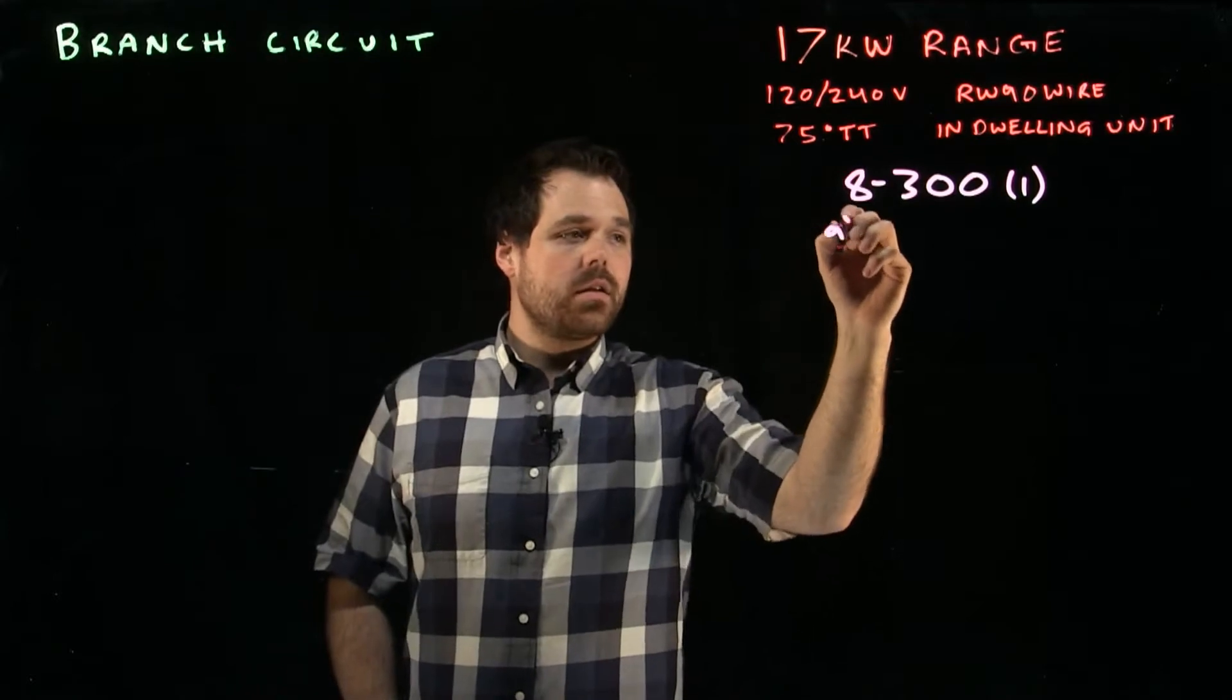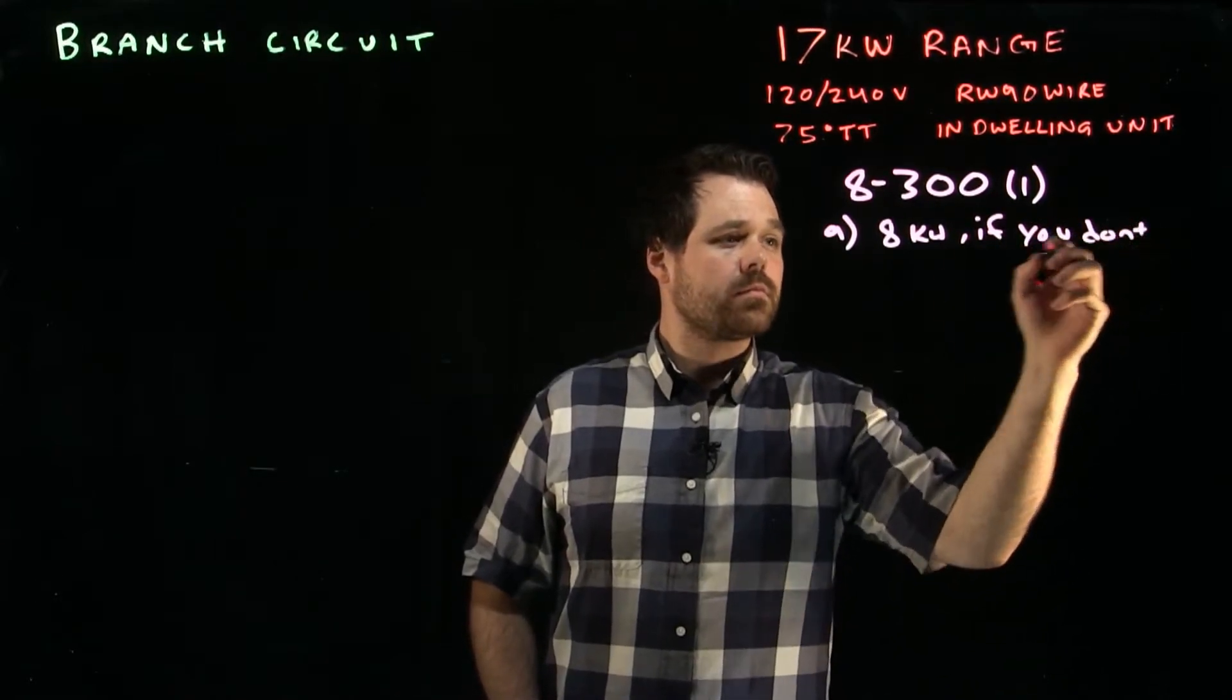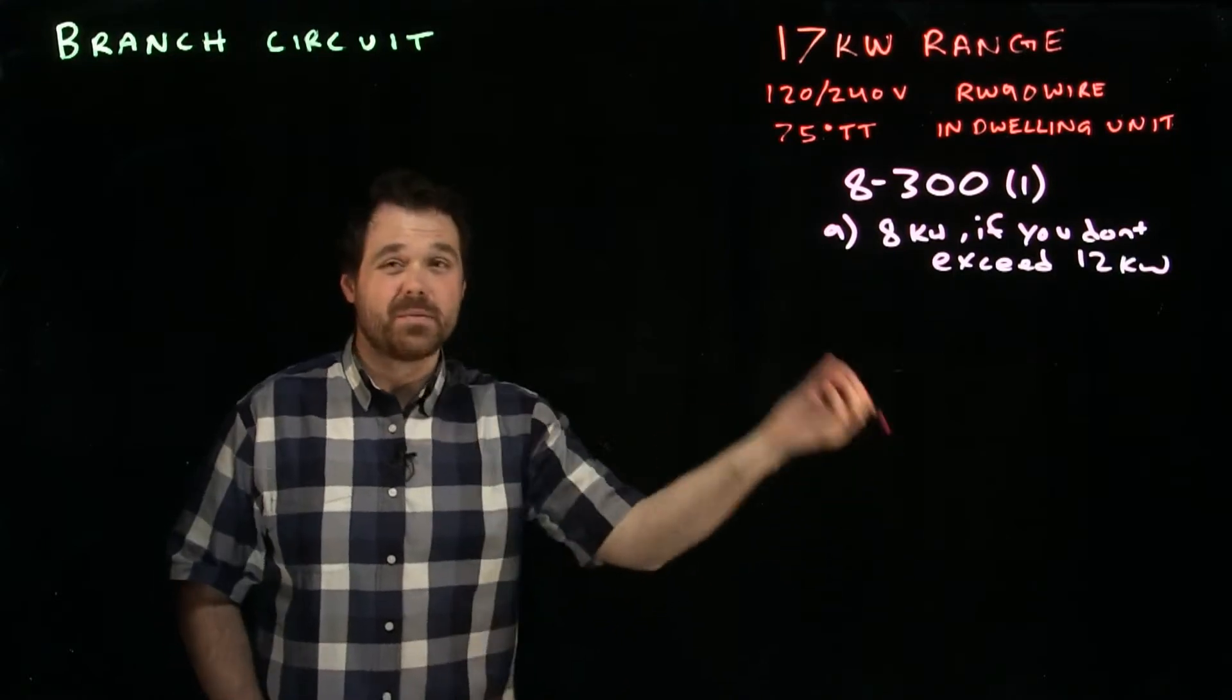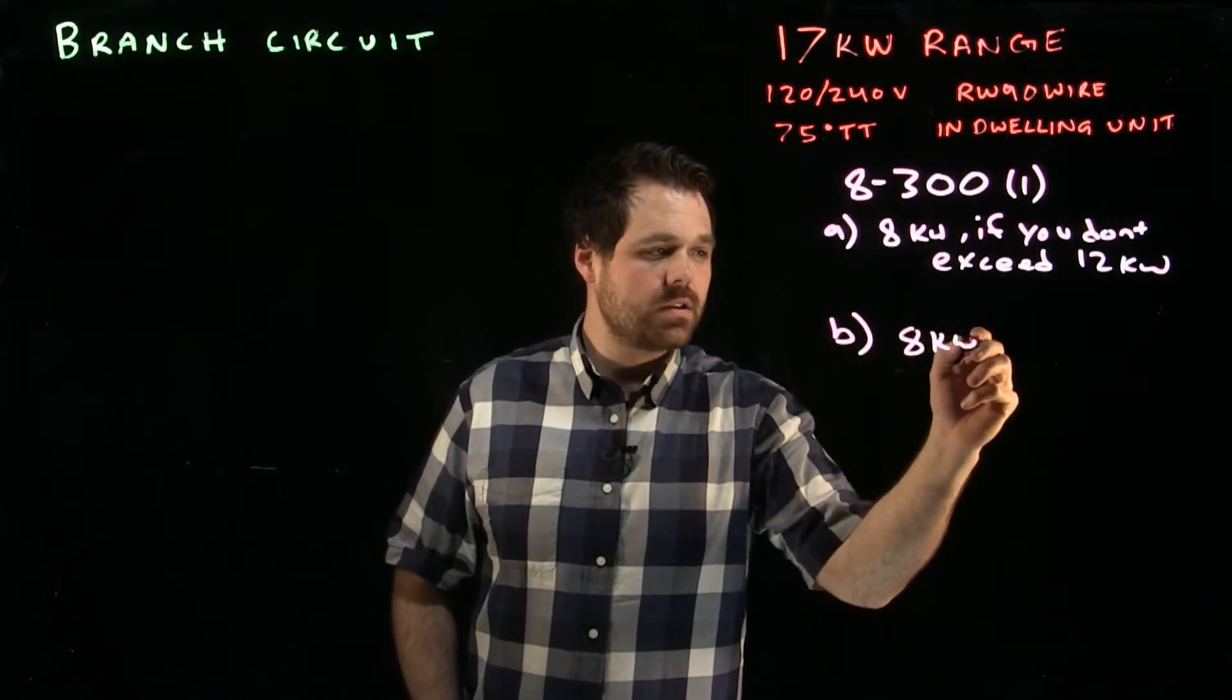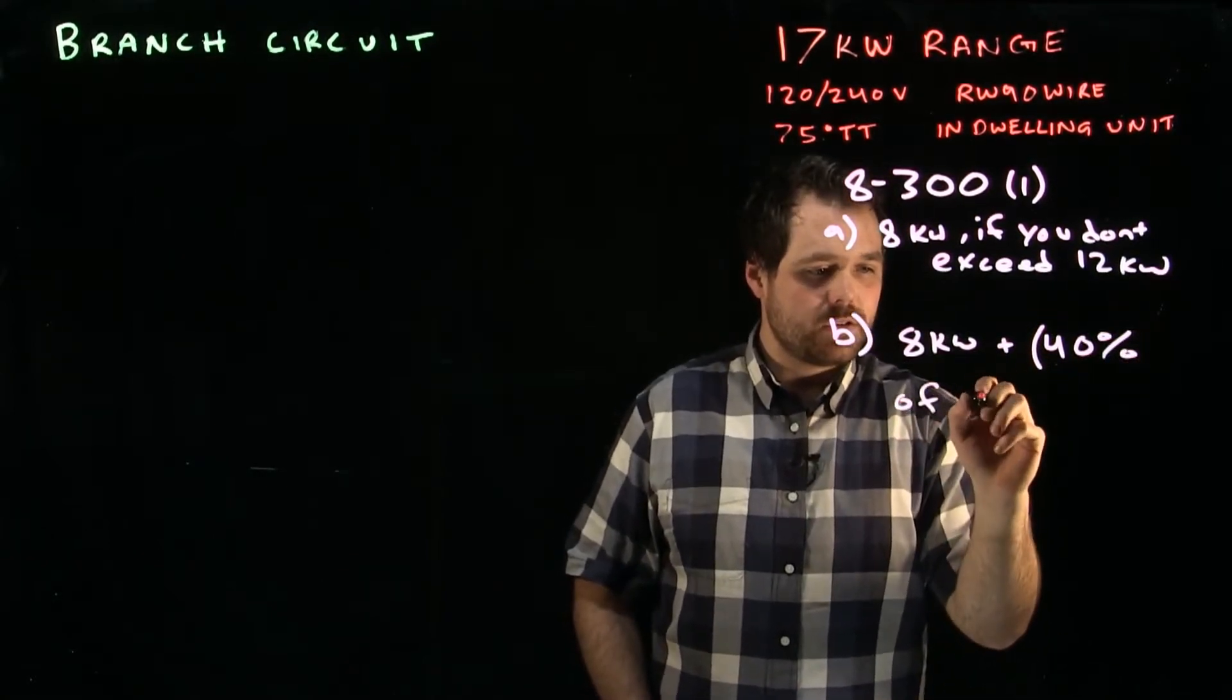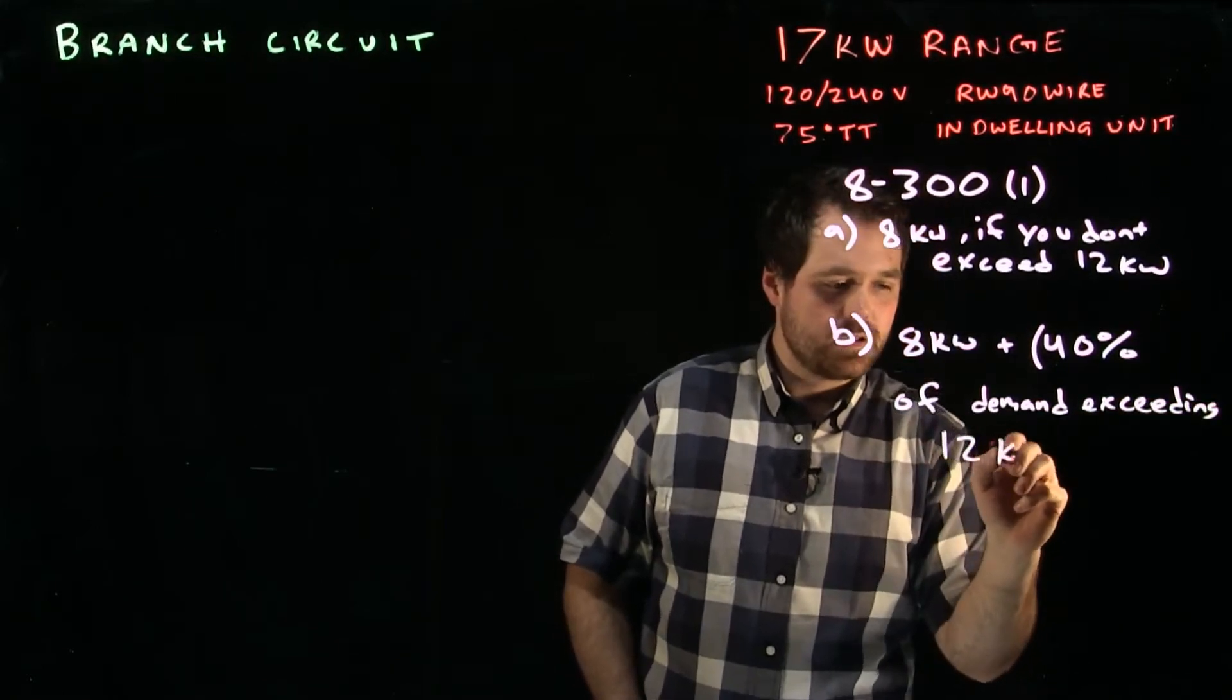It says 8 kilowatts if you don't exceed 12. So if I have a range and it doesn't exceed 8 or 12 kilowatts, then I would count it as 8 kilowatts. And B says 8 kilowatts plus 40% of demand exceeding 12 kilowatts.